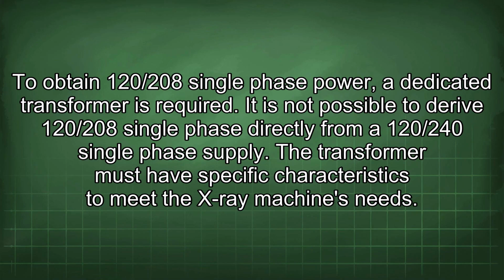To obtain 120/208 single-phase power, a dedicated transformer is required. It is not possible to derive 120/208 single-phase directly from a 120/240 single-phase supply. The transformer must have specific characteristics to meet the X-ray machine's needs.